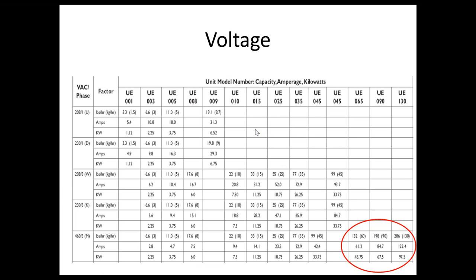The higher the voltage, the more pounds per hour capacity. At 460V there are several choices. A lot of times we're asked to size or replace a humidifier based on the nameplate rating — but designs change over time, and the amp draw may differ. If replacing a unit, make sure you know what kind of amp draw and circuit — breaker, fuse, whatever is feeding the system — to help you design correctly.